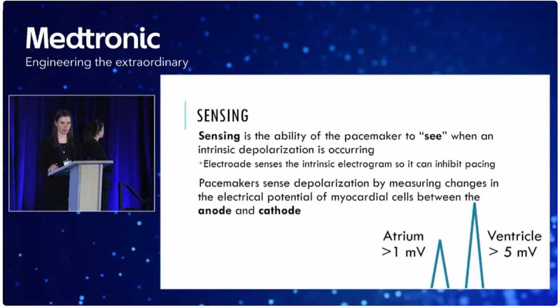In the ventricle, above 5 millivolts, but obviously if it's 10 or 15 or 20, you're pretty happy as well. Well, what about sensitivity? A lot of people don't like thinking about sensitivity because it's a little backwards and it can be a little bit confusing. So that's the level an electrogram has to exceed in order to be sensed by the pacemaker. And we program the sensitivity after we measure the size of the intracardiac electrogram. And we usually set it at half the P wave or half the R wave.